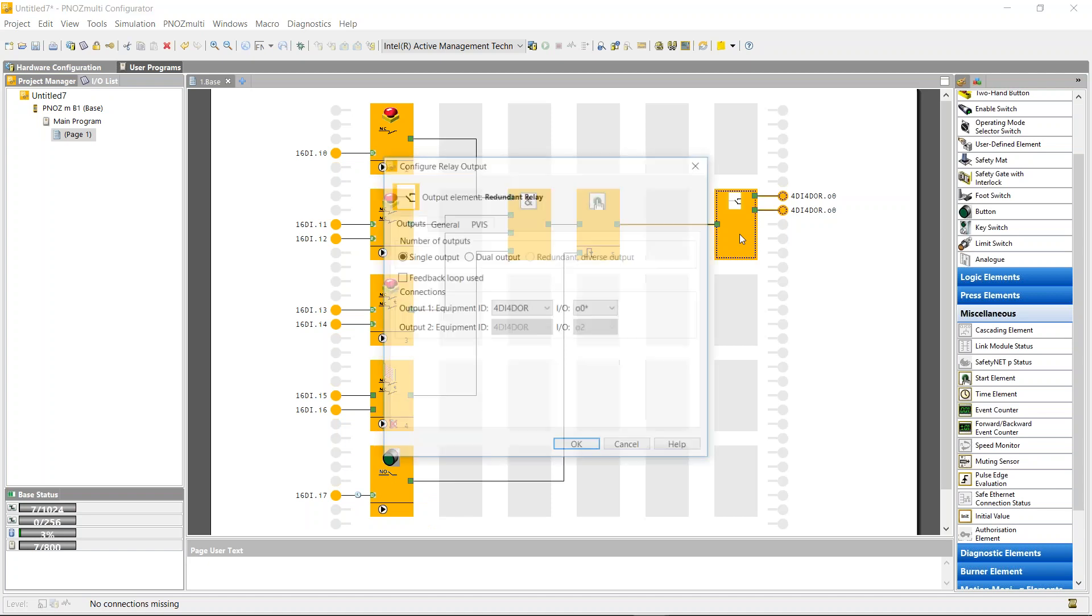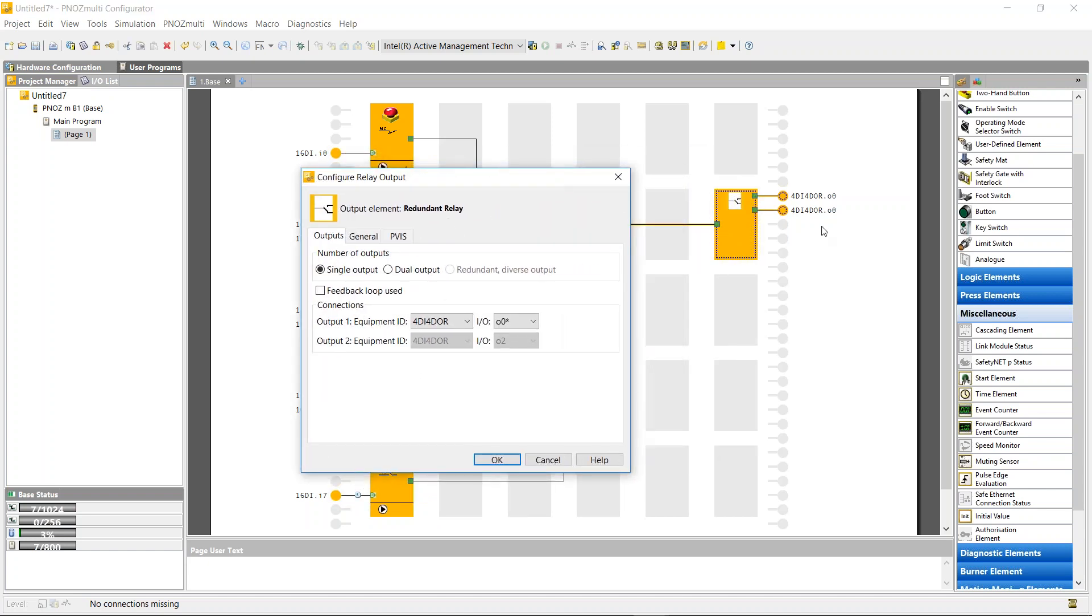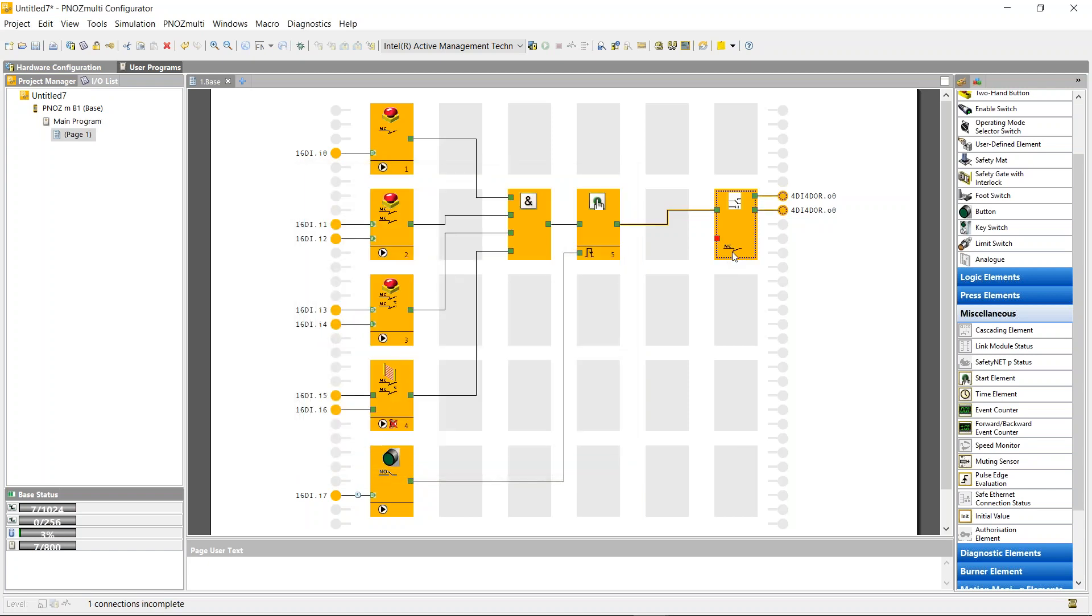If I wanted to put in feedback into the contactor, so if I wanted the normally closed part of the contactor circuit to be monitored to make sure my contactor isn't sticking, I could put in a feedback loop into the output. This feedback loop is on the normally closed part of the contactor.